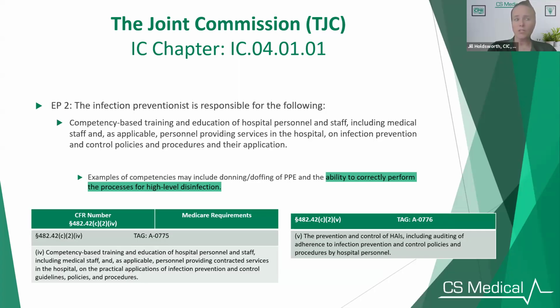For those of you that have been doing this for a long time, they used to just walk in SPD, hold a tissue up to the vent to make sure decon had negative pressure, and they'd give us a thumbs up and they'd walk out. Now they really know what to look for. So below, you can also see how it correlates with CMS. So this is important. Understanding where your risk points are with high-level disinfection, how you can simplify it, and how you can be compliant is just as important as knowing that it's better for your patient safety.